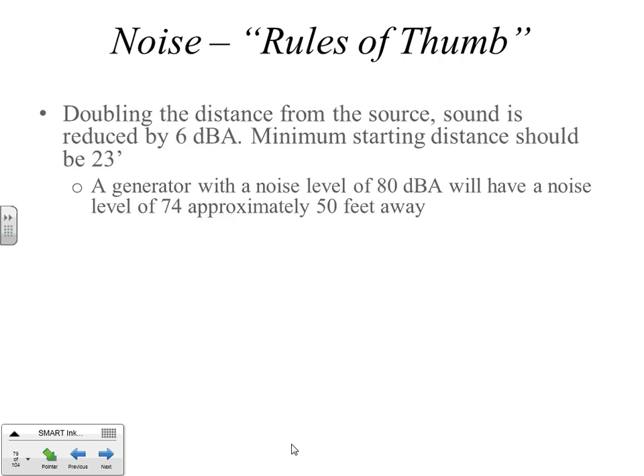Some rules of thumb. Doubling the distance from the source, in other words, from the, let's say, the generator set, sound is reduced by 6 dBA. Minimum starting distance should be 23 feet. I added that note later. Example is a generator with a noise level of 80 dBA will have a noise level of 74, approximately 50 feet away.